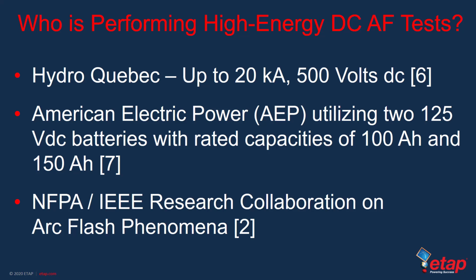Now we need to discuss how this new DC arc flash arena fares in terms of high energy DC power systems, where the fault currents actually reach levels as high as 20,000 amps or higher. These are some of the organizations, as shown in this slide, who have recently published results of research from laboratory test conditions on DC arc flash tests.